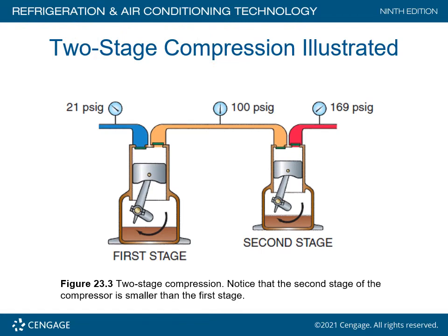Figure 23.3 in the textbook illustrates a standard two-stage reciprocating compressor. Notice the second stage is smaller than the first. The first stage draws vapor in at 21 PSIG, compresses it up to 100 PSIG, and discharges directly into the second stage, which increases pressure to 169 PSIG. Remember, this is utilized when you have more than a 10 to 1 ratio.